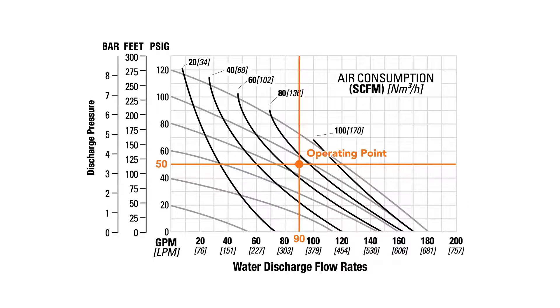From this operating point, the curve will identify the required air inlet pressure to achieve the desired performance by following the gray curved axis. In this example, the operating point is between the 80 PSIG and 100 PSIG air inlet curves. Thus, the required air inlet pressure to operate the pump would be 90 PSIG.